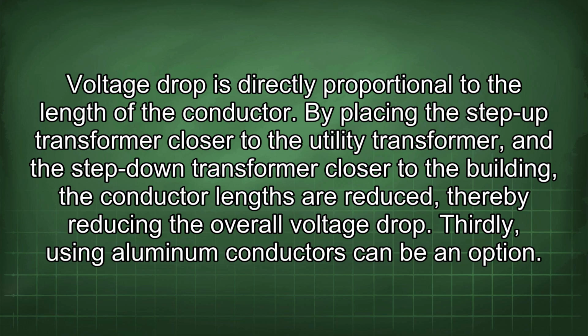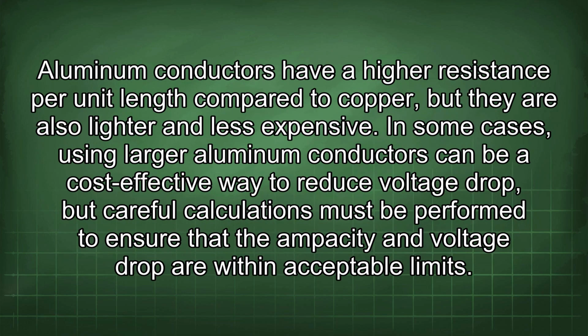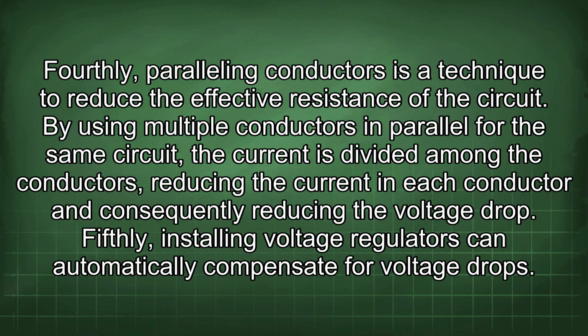Thirdly, using aluminum conductors can be an option. Aluminum conductors have a higher resistance per unit length compared to copper, but they are also lighter and less expensive. In some cases, using larger aluminum conductors can be a cost-effective way to reduce voltage drop, but careful calculations must be performed to ensure that the ampacity and voltage drop are within acceptable limits. Fourthly, paralleling conductors is a technique to reduce the effective resistance of the circuit. By using multiple conductors in parallel for the same circuit, the current is divided among the conductors, reducing the current in each conductor and consequently reducing the voltage drop.